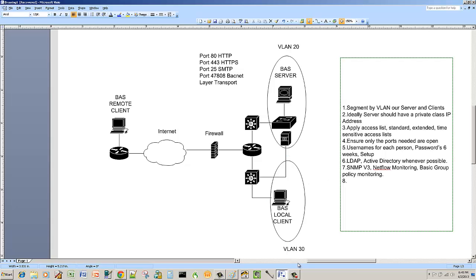But if you are really hard to get into and your neighbor has his BAS system, and literally I've seen this, on his company public website he's got an exposed HTML page that has a URL link to his control system, and then you can just Google the vendor password for that control system and log in. Yeah, they're probably going to focus on that guy.